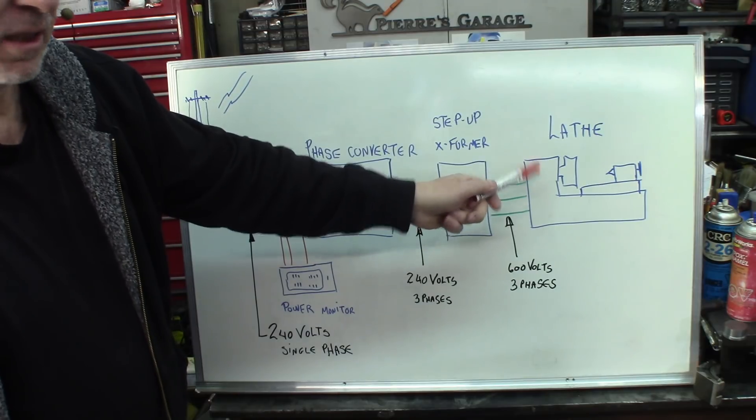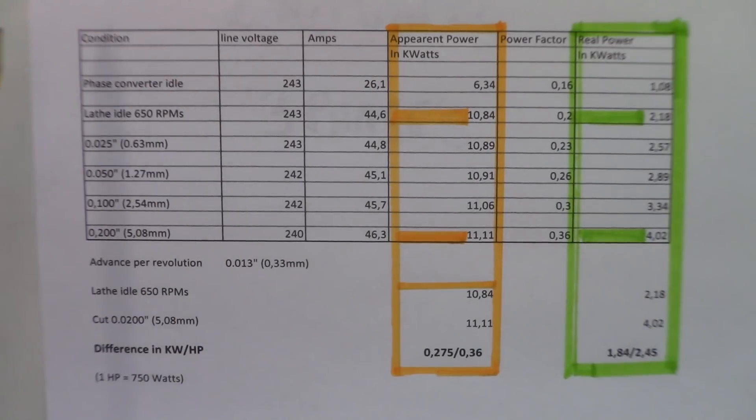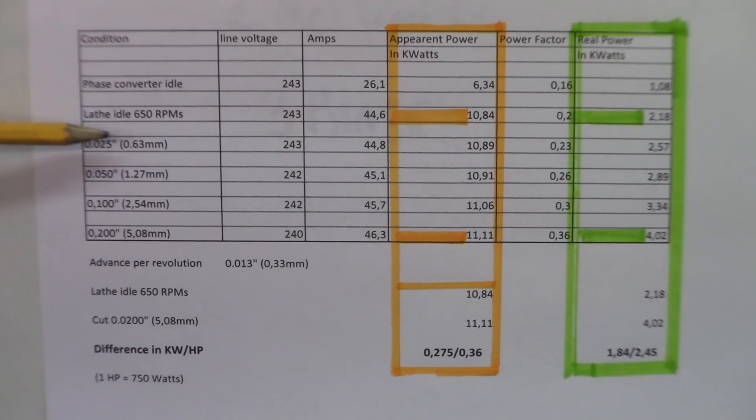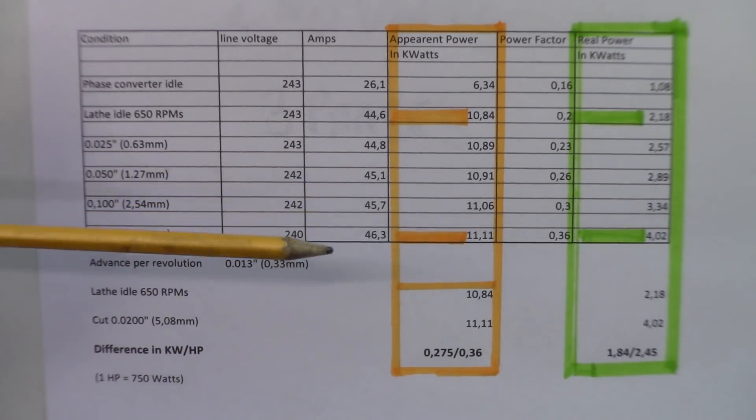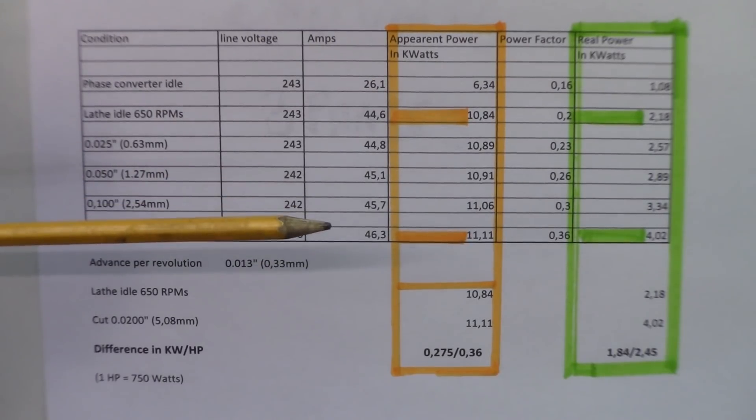I've compiled everything onto this little board here, the condition, which is like phase converter idling, the lathe just idling, and all the different size of cuts here, the line voltage according to the conditions, the amps from the line monitored at the entrance of the whole system, the apparent power here, which is the result of these two raw numbers multiplied by each other, according to the formula. So this formula, if you take it straight just like that, it doesn't take into account the phase shifting.